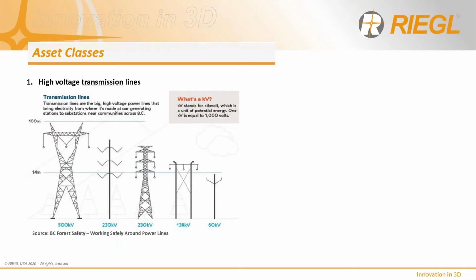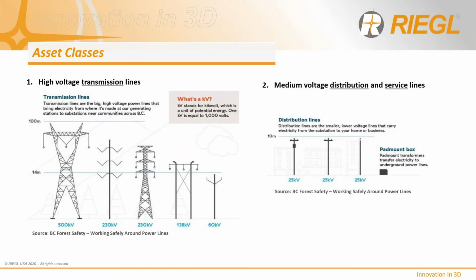Power lines are generally broken into two classes: transmission and distribution. The larger transmission lines carry high voltages ranging from 60 to 150 kilovolts, up to extremely high voltages of 500 or even 700 kilovolts or more, from the generating station to substations, where step-down transformers reduce the output voltages for distribution to communities and urban centers. Smaller service lines emanate from the distribution network to homes and businesses, generally lumped into the distribution class but of much lower voltages.